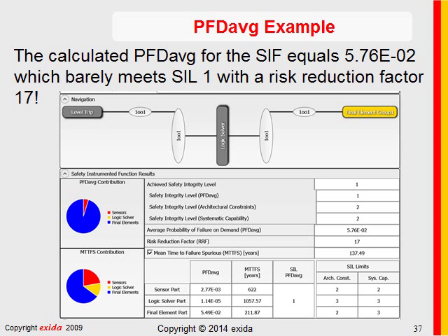Now, I have done some sensitivity analysis, and all of them have an impact, but I will tell you that the impact of proof test coverage is most significant. Given our 1 year and our 5 year, the impact of bypass is not that significant in this case. I think it's a big deal. I think it's very important that a competent, responsible, and ethical engineer use and account for all the variables.